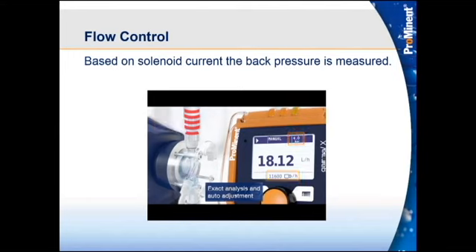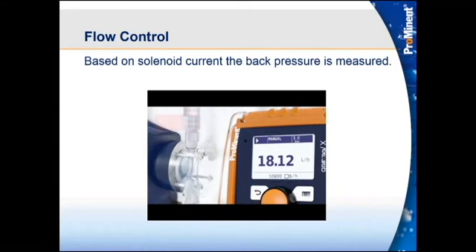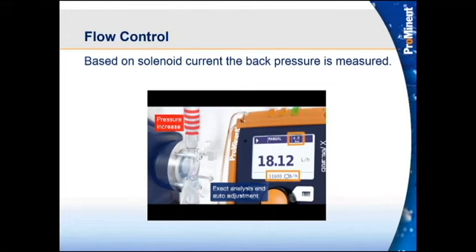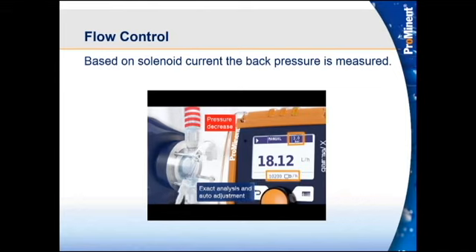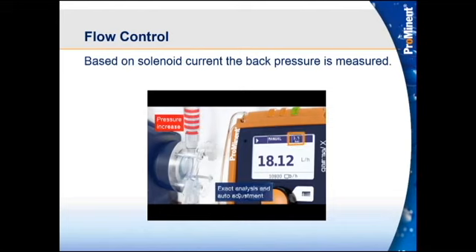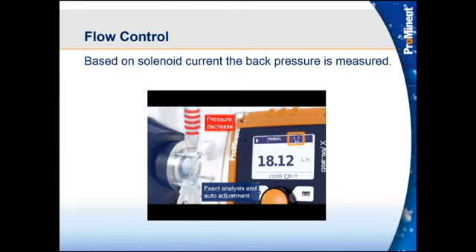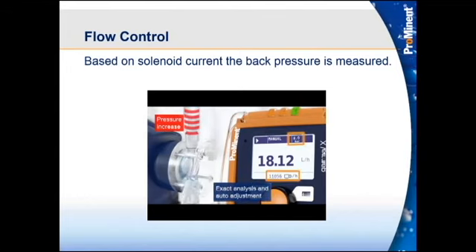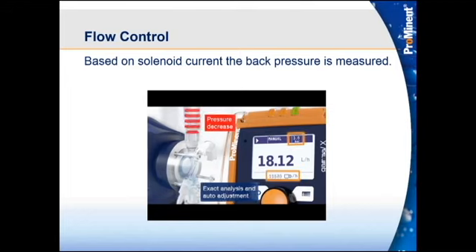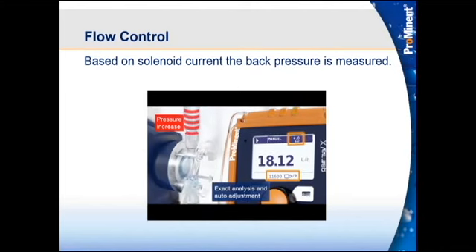We had a pump running in our lab at somewhere around 58 PSI on our gauge, and the pump read exactly what the gauge read. So there's a lot of systems out there where people don't have gauges on their systems. This would allow us some flexibility in having somewhat of an idea of what that pump's pumping against. You also notice in this animation, they'll decrease the pressure. If we decrease the pressure, it's going to be easier for the pump to pump, so it's going to put out more, so it will decrease the actual frequency. Along the same lines, if pressure were to go up, we will need to increase that frequency, so we'll compensate for that reading on the screen.